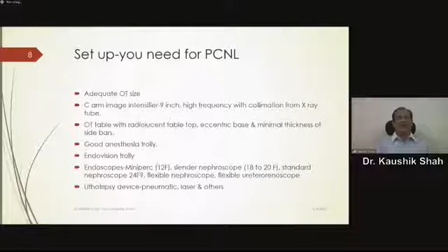Nowadays, a lot of stones are less than 2.5 centimeter, and the majority of the stones can be taken care of by a 12 French nephroscope, either from Storz, Wolf, or Olympus. Of course, the slender nephroscope of 18 to 20 size from Wolf and Storz is also very useful. Many have a standard nephroscope of 24. If they want to reduce the track size, it is not possible. So I recommend those who have a big nephroscope to invest in a small nephroscope, either the Miniperc or a slender, or preferably both.